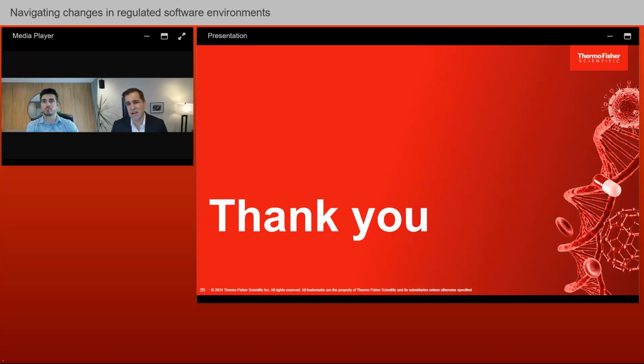So even though it's not pre-approved, you do pre-approve what you're trying to challenge with the system. What you're not doing is scripting exactly the path you will take to get there. You're using an expert to walk through the system, and then they document their as-found results, because those features are lower or medium risk, so that's an acceptable approach.